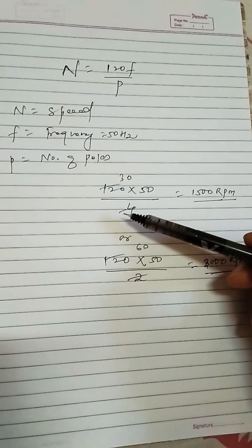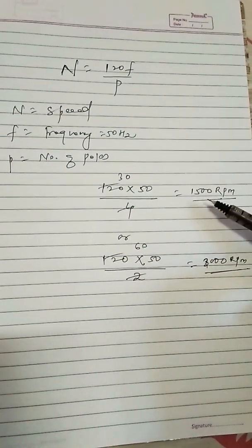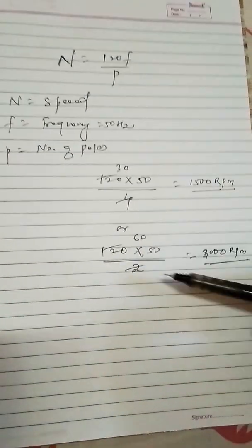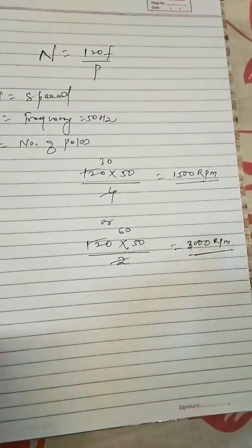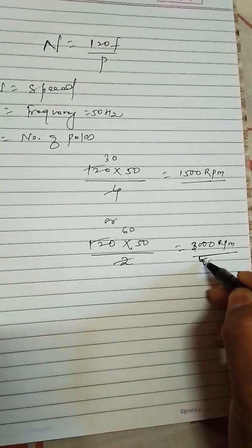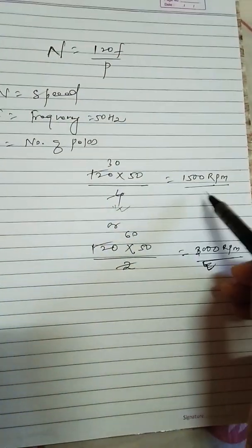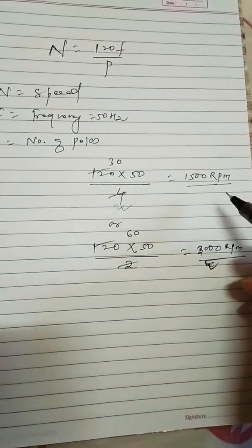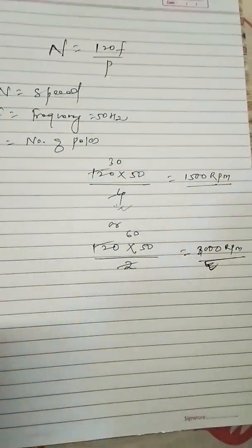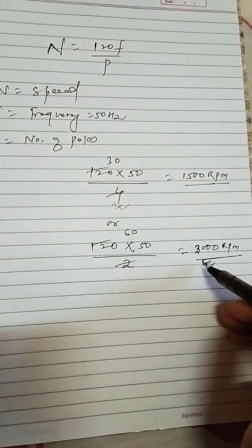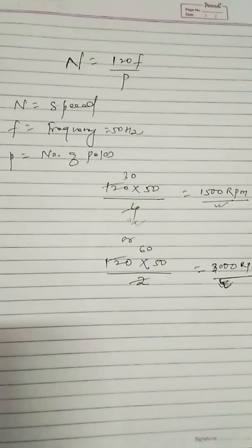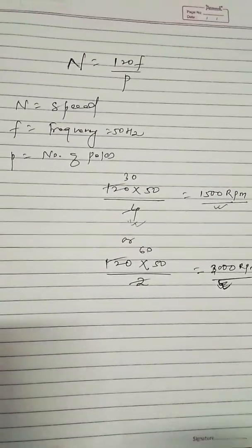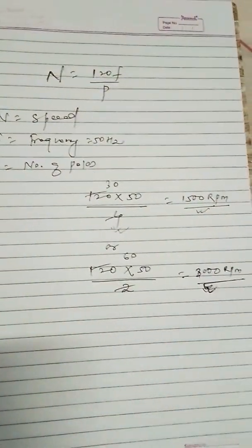If we have a four-pole generator, the turbine should rotate at 1500 RPM. If the number of poles is 2, then the turbine speed will be 3000 RPM. In some cases, if the turbine RPM is 3000 and we have a four-pole generator, we use a gearbox between the turbine and generator to reduce speed from 3000 to 1500 RPM. In that way, we calculate the number of poles or speed requirement.